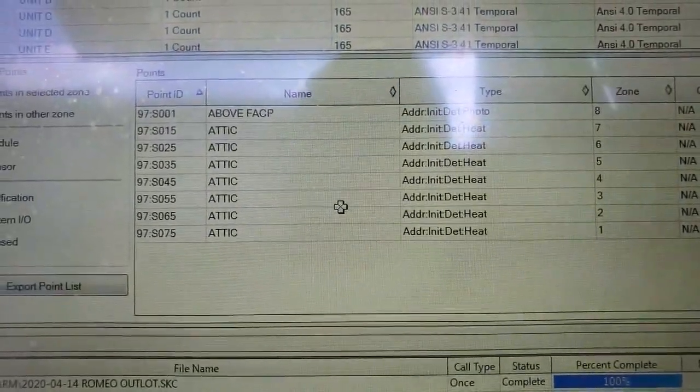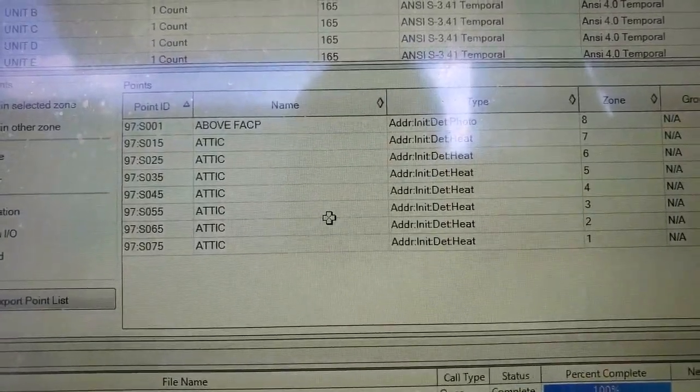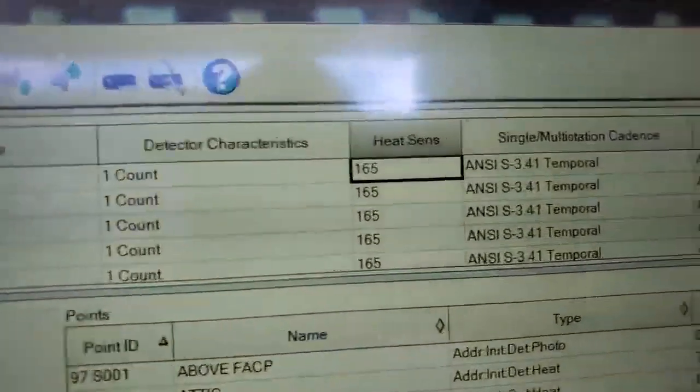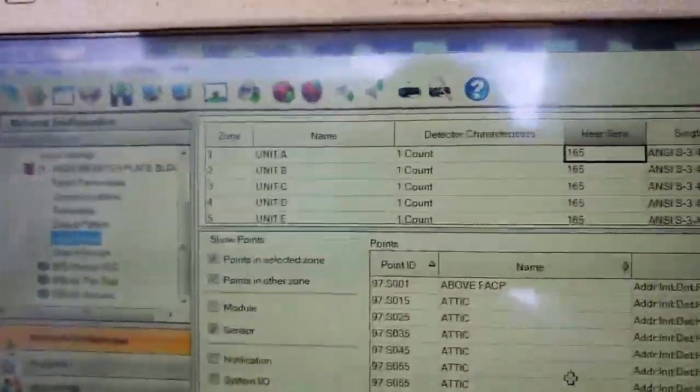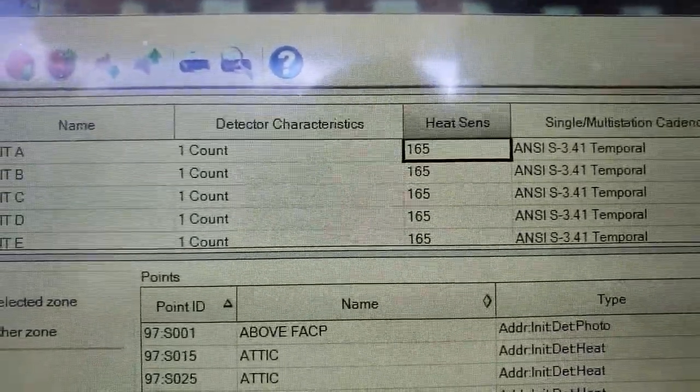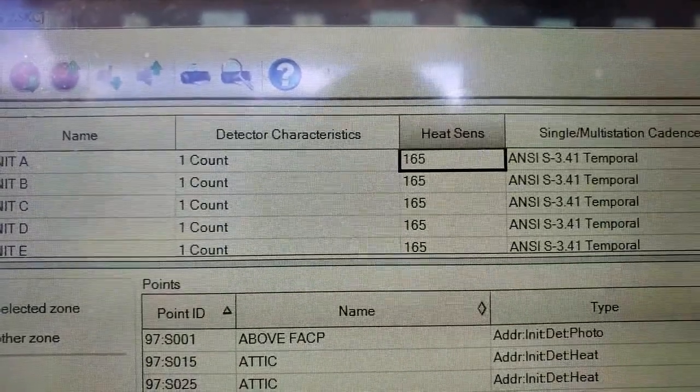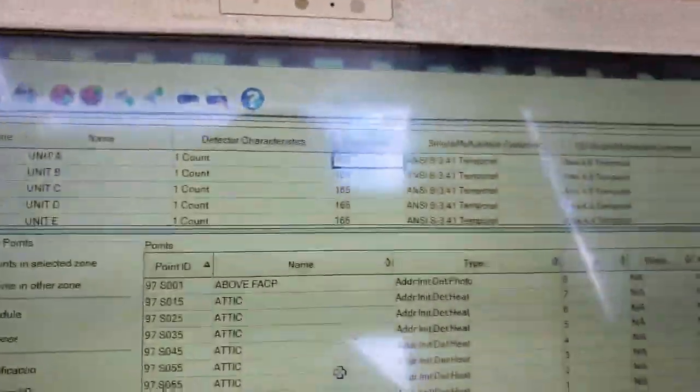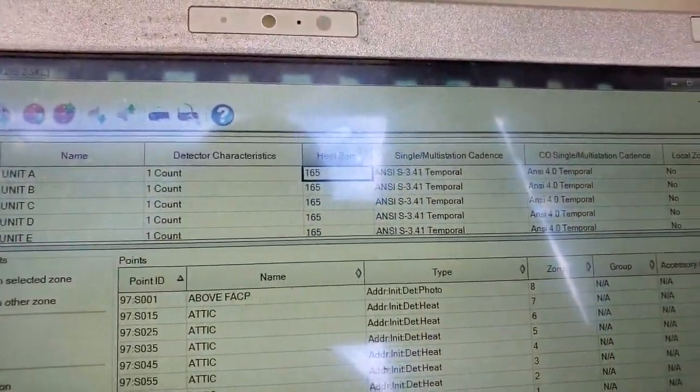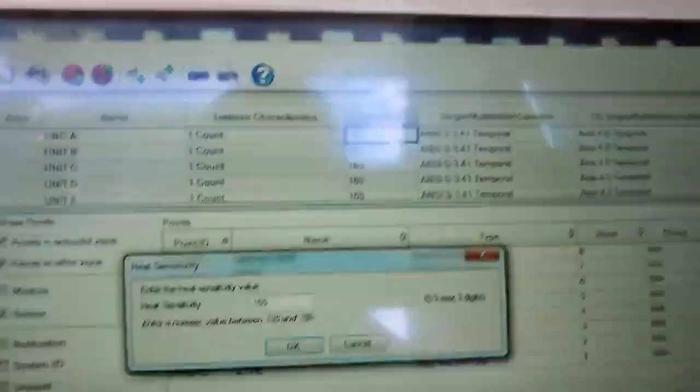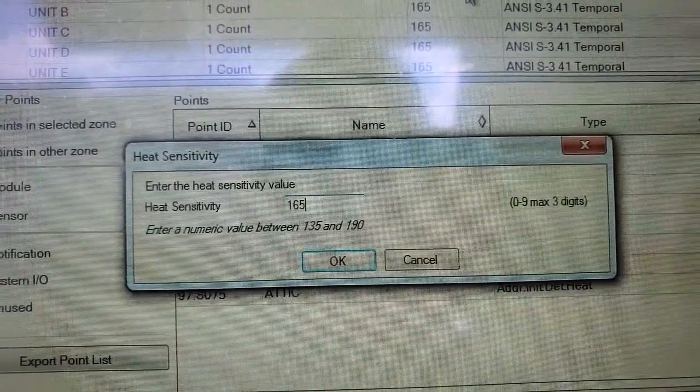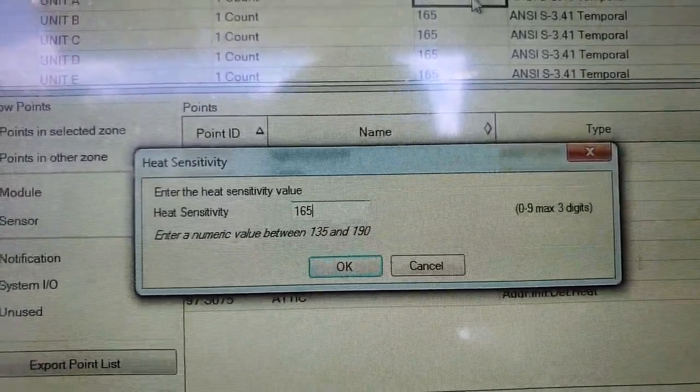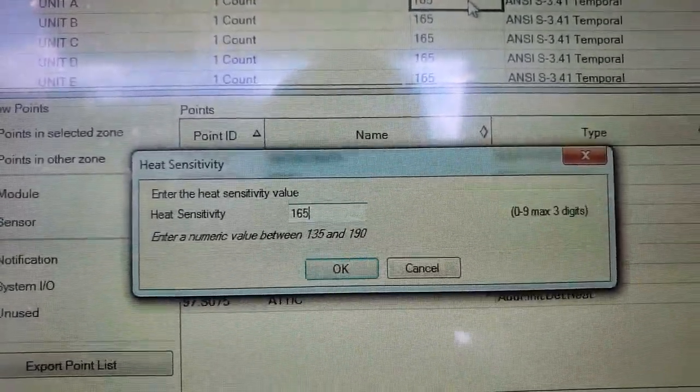So here we go. Here's some devices. They are straight heat detectors, but under the zones, the input zones, they have this nice little column here, heat sensitivity, which when you right-click on this, it comes right up and it says, enter a numeric value between 135 and 190.